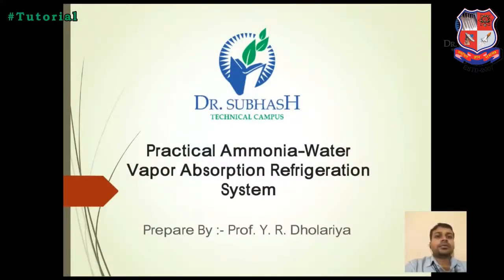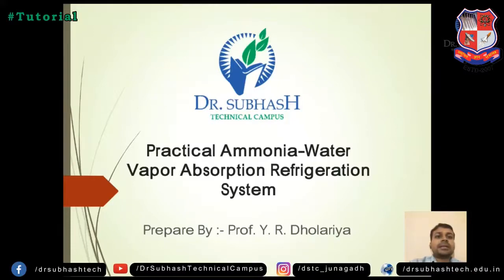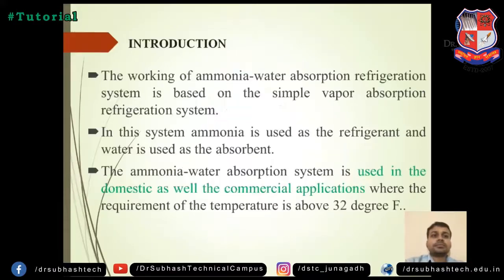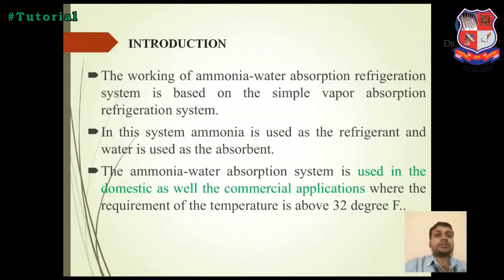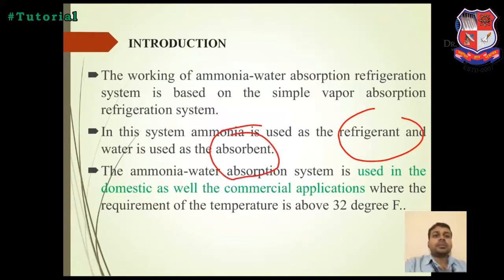Hello, good morning. Today we have to study the practical ammonia water vapor absorption refrigeration system. Introduction: the working of the water ammonia vapor absorption refrigeration system is based on the simple vapor absorption refrigeration system. It's a very simple cycle, not as complicated as a VCR system, the vapor compression refrigeration system. In the system, ammonia is used as a refrigerant and water as an absorber. There are two working fluids: ammonia is the refrigerant and H2O is the absorber.